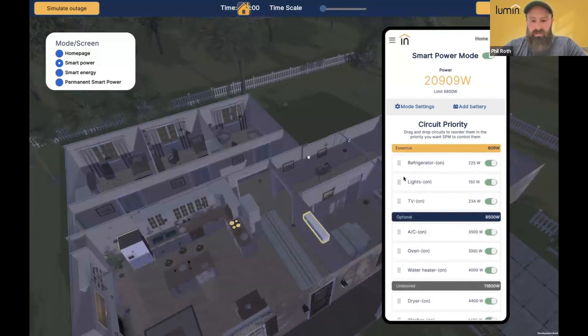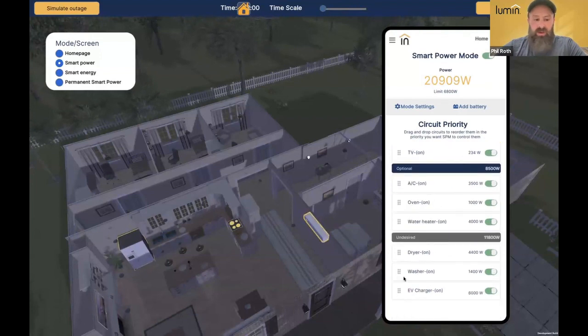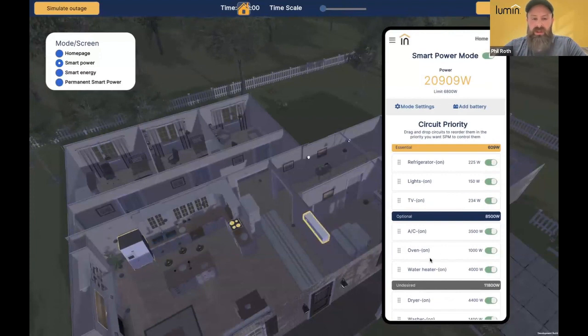Our undesired loads are ones that load shed as soon as the grid status changes, so as soon as the power outage occurs, dryer's off, washer's off, EV charger is off. And our optional loads, it's more of a dynamic setting where these will turn on and off as capacity is available with your battery-based inverter. This particular demonstration scenario, we have a battery-based inverter with 6,800 watts of capacity.